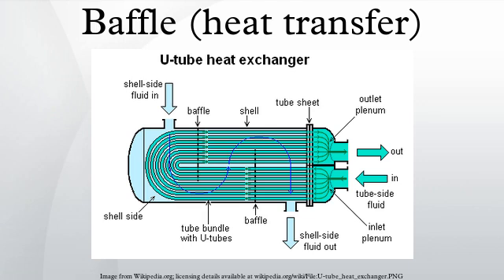The minimum baffle spacing is the greater of 50.8 mm or one-fifth of the inner shell diameter. The maximum baffle spacing is dependent on material and size of tubes.